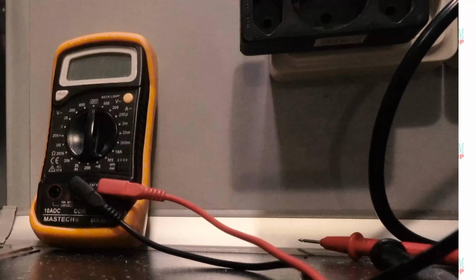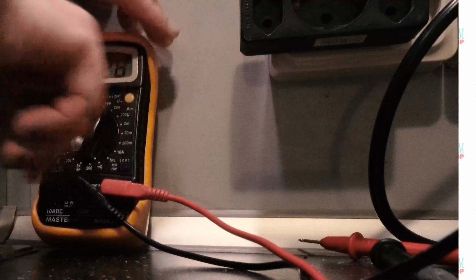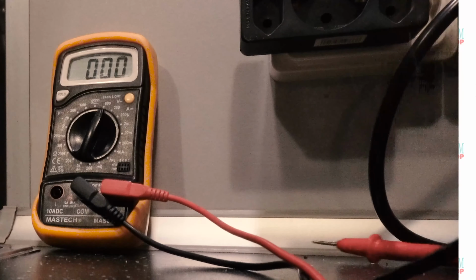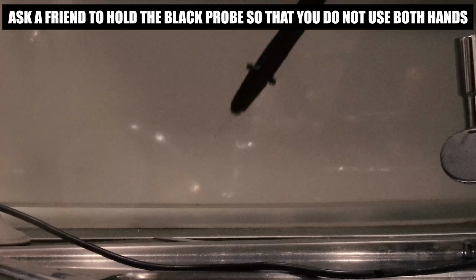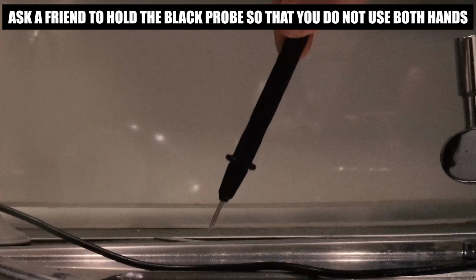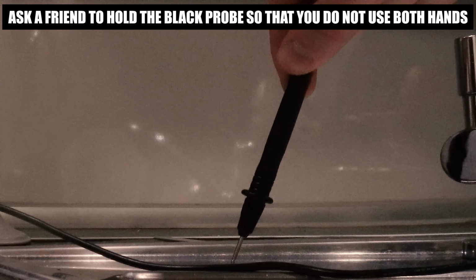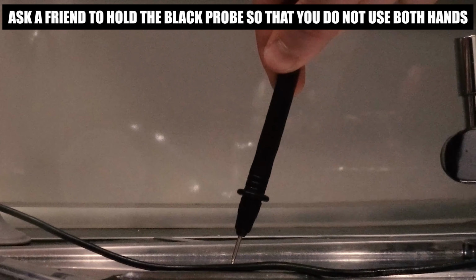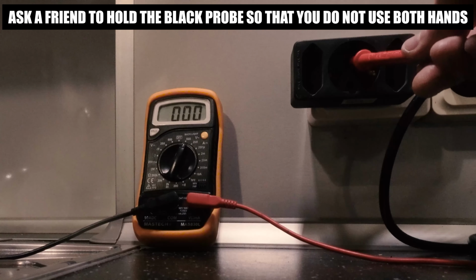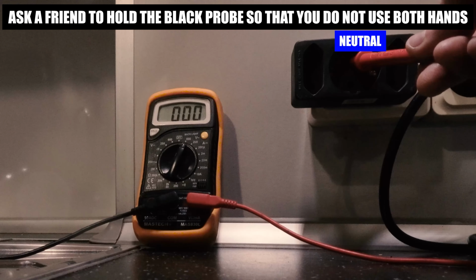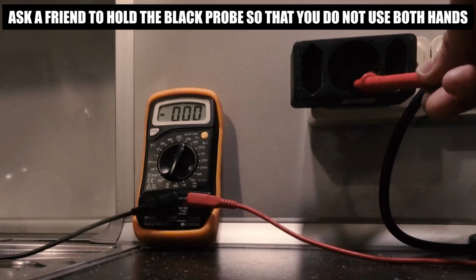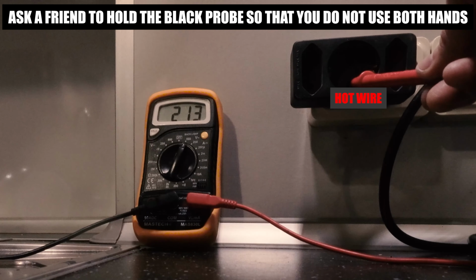If you need to determine the hot wire in the wall outlet and you have no indicator screwdriver at hand, use this method. Put your DMM into AC voltage mode, the highest range. Then attach one probe to a radiator or a water pipe, and use the second probe to touch the outlet's contacts, one by one. Whichever contact you get a voltage reading on is the hot wire.